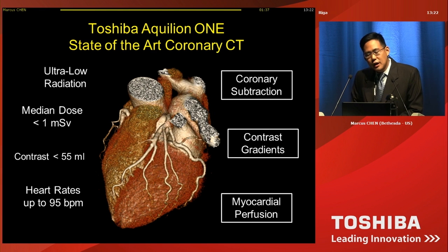In conclusion, the Aquilion ONE scanner provides state-of-the-art CT. It's able to do ultra-low radiation doses of less than one millisievert. The contrast dose is also very low — less than 55 cc of contrast. We've done heart rates up to 95 beats per minute. And with this type of technology, you're able to do novel techniques such as coronary subtraction, evaluate contrast gradients, or do myocardial perfusion. Thank you for your attention.